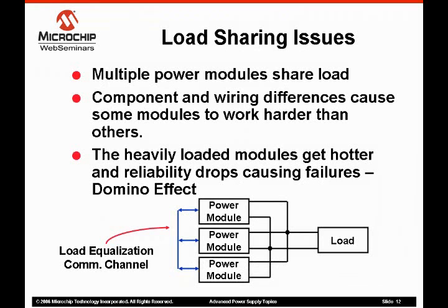Load sharing connects the outputs of two or more power supplies together to a power load. Usually there are more modules with more total power capability than required by a system. The amount of redundancy is dictated by system reliability goals.